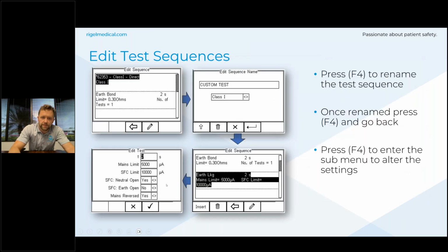Again, this shows you how the limits are shown up on the menu, so you can go in there using the keypad, change the mains limit, change the single fault condition limit, and also make any edits to the fault conditions from each specific test. From there, you can change the name of it, and it will be there within the auto sequence. You can select that from the menu and run through the sequence from there on in.